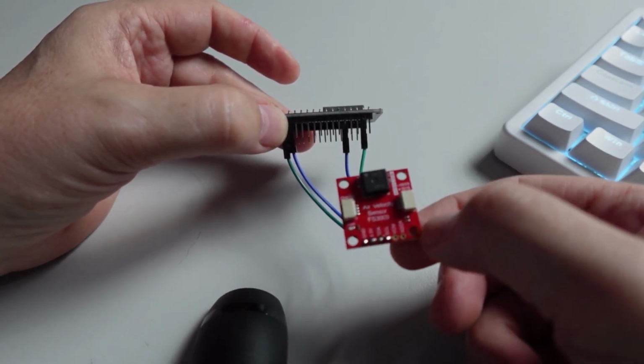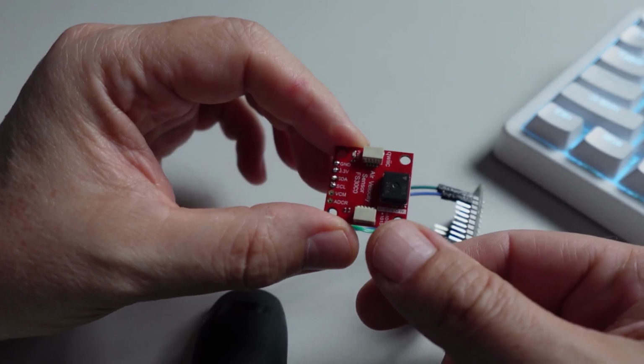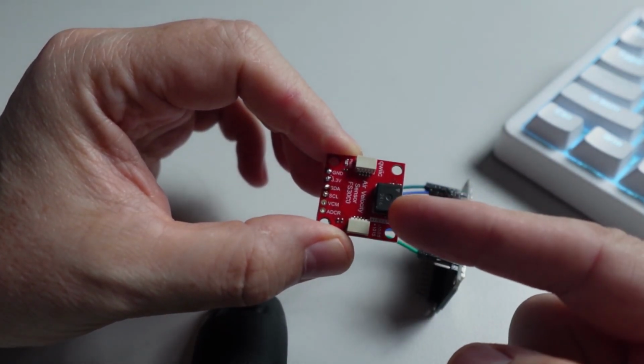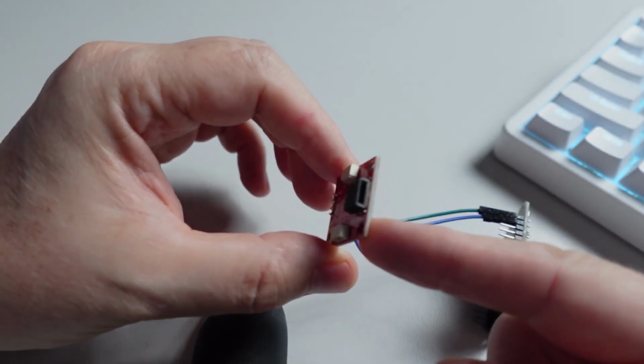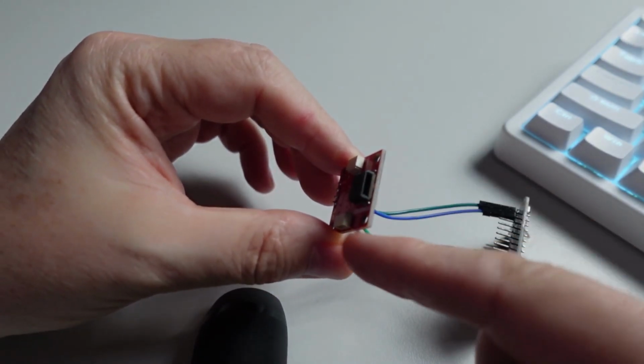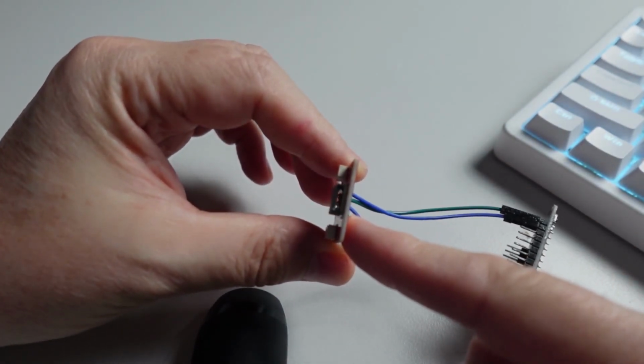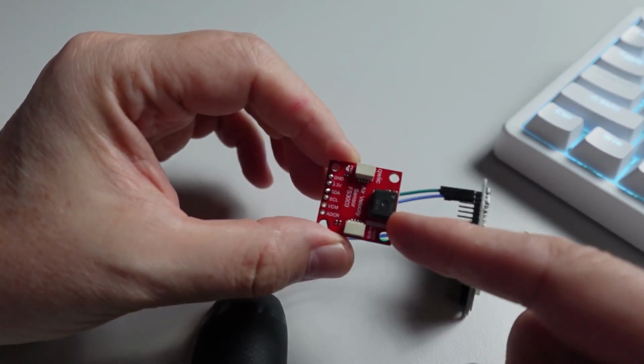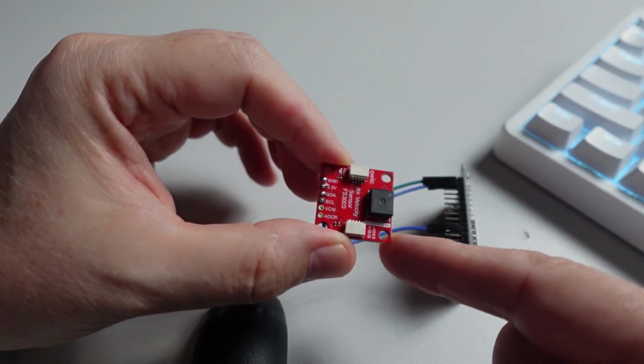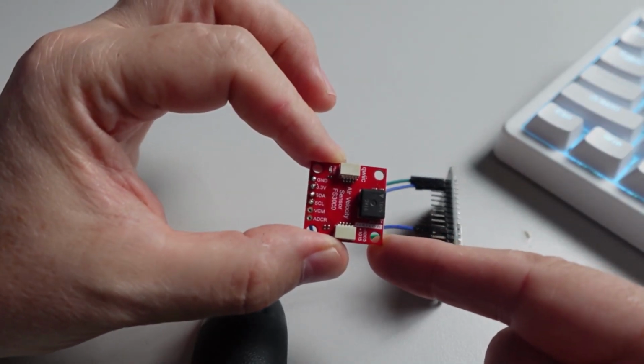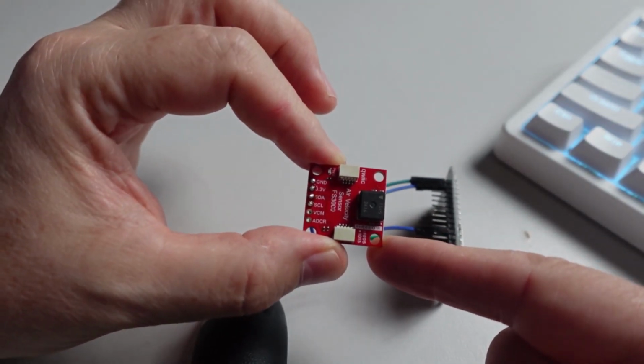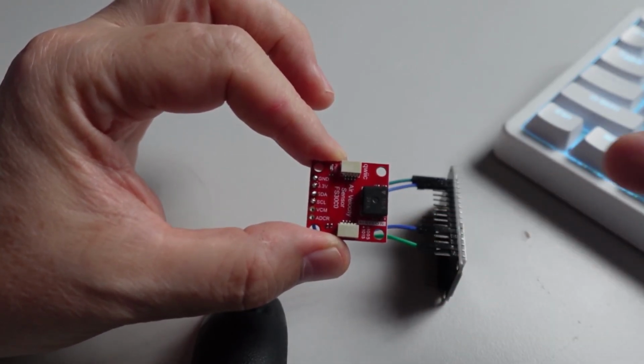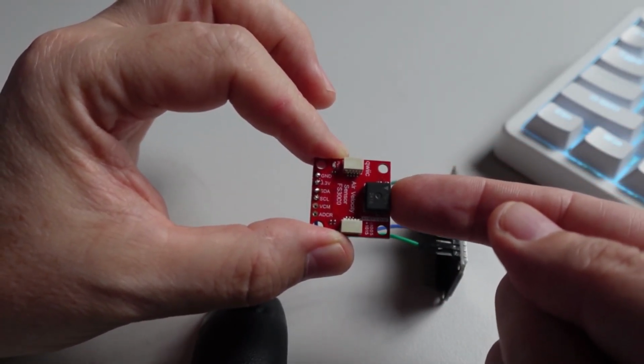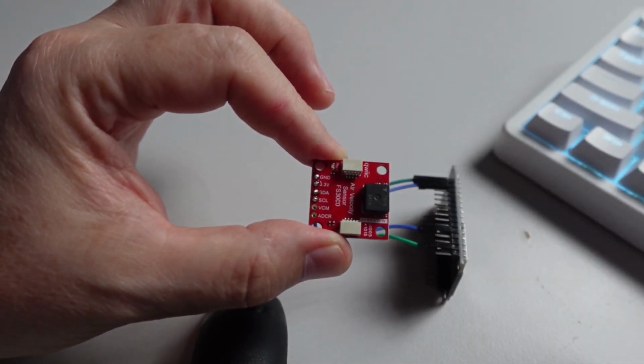SDA to SDA. Now, if you look closely at the sensor, you'll see that there's a little arrow pointing that way. So the airflow needs to come in on this side, move through that little gap there, and then exit on the other side. It's very important when you install this into the pipe in your airflow duct system that the flow is coming along here and heading directly through there and out of the other side.